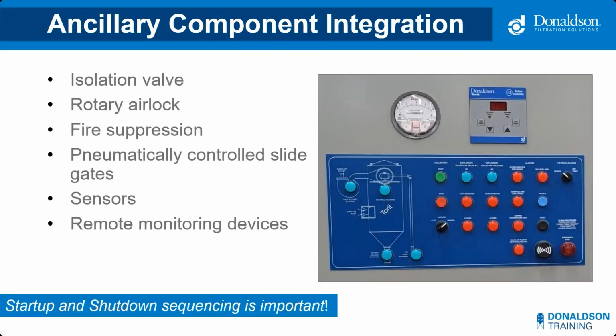Now, if the system has ancillary components, you can specify that they're integrated with the control panel. Explosion mitigation devices like the fire suppression system, isolation valves, and explosion vents are incredibly common and can be programmed on the control panel to make sure the system will shut down appropriately if there were to be an event. On that topic, the startup and shutdown sequencing is very important.